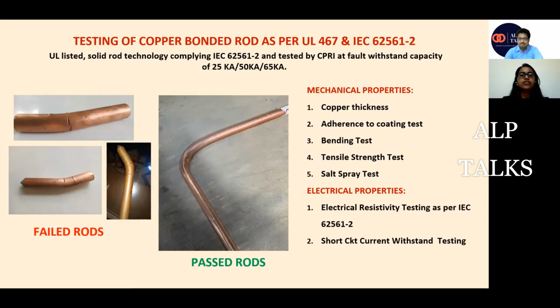If I'm talking about the mechanical properties, first of all is the copper thickness. It should not be less than 250 microns. There are other tests also, like the adherence to coating test, in which we check that on beating the rod again and again, the copper coating should not peel out. Another test is the bending test: after bending, the copper coating should not crack anywhere and it should not be removed from the steel rod. Then only it will be properly molecularly bonded over steel and serve the purpose of using this material.